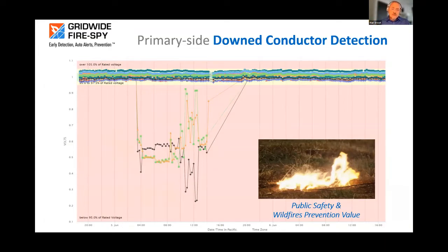It was downstream on the secondary side of a transformer, a polyphase in this case. The conductor let loose, dropped into the forest canopy, burned its way through all the way to the forest floor, and created a wildfire that unfortunately went on for hours because it was in a somewhat remote area when it began. And it's happening in the middle of the night. Nobody's out to see it, and this thing just starts going.